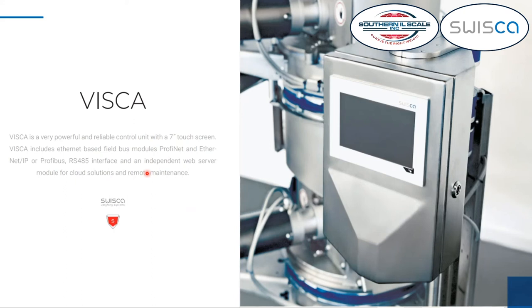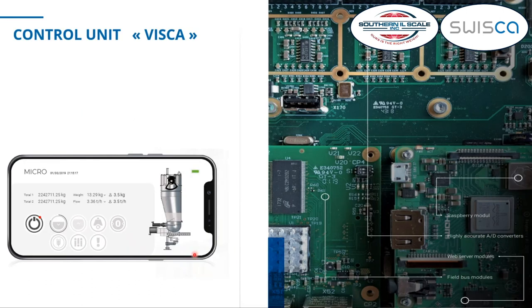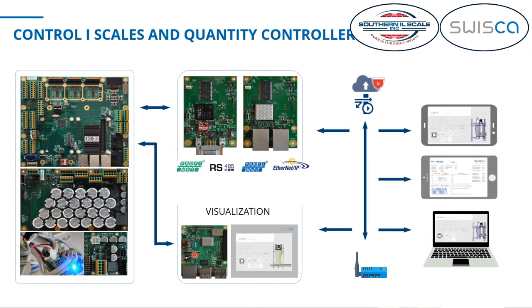All our scales use the same scale control — Scale Control Visca. There is a seven-inch HMI locally at the scale where you can access all the parameters and monitor the system, or you can also connect remotely with your mobile device when the scale is connected to your network. There is a main control responsible for the whole scaling application, and two interfaces: one for connecting to a PLC, and the other for visualization, internet connection, and remote access to give assistance to operators.